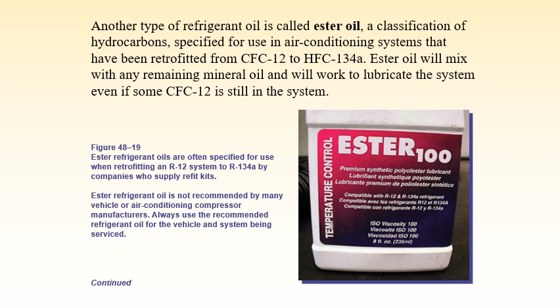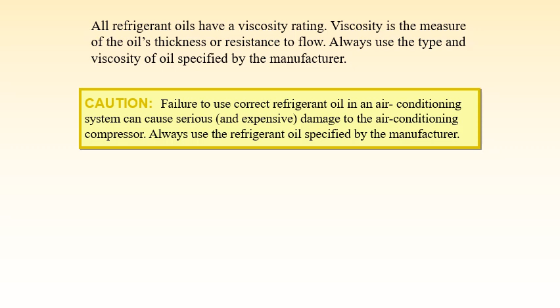Now all refrigerant oil has viscosity ratings. What is viscosity? Viscosity is the measure of the oil thickness or the resistance to flow. You have to always use the type and viscosity of oil which is specified by the manufacturer. Another important note you have to take down: failure to use the correct refrigerant oil in an air conditioning system can cause serious, that is expensive, damage to the air conditioning compressor. Always use refrigerant oil which is specified by the manufacturer.